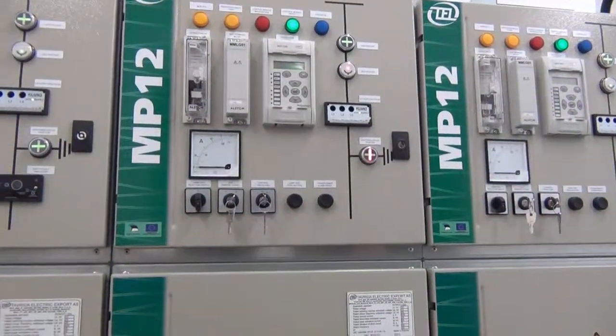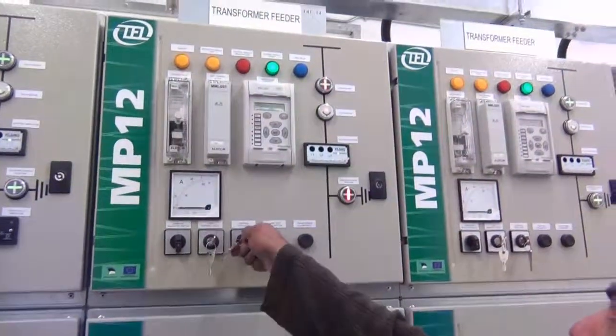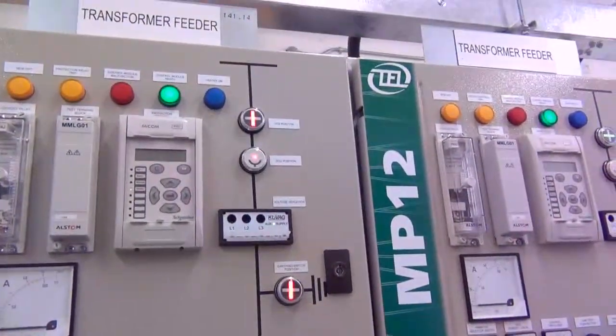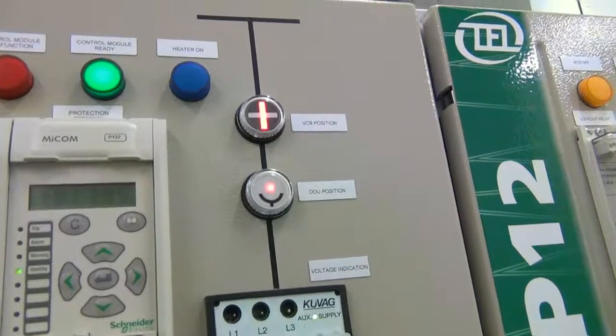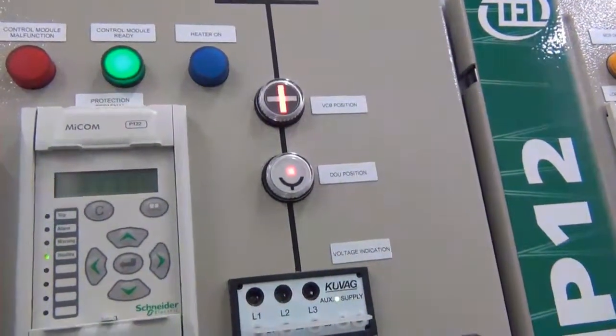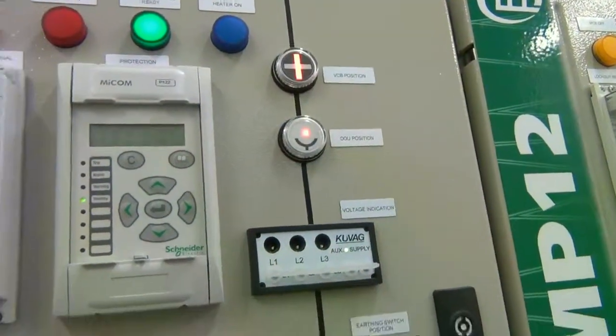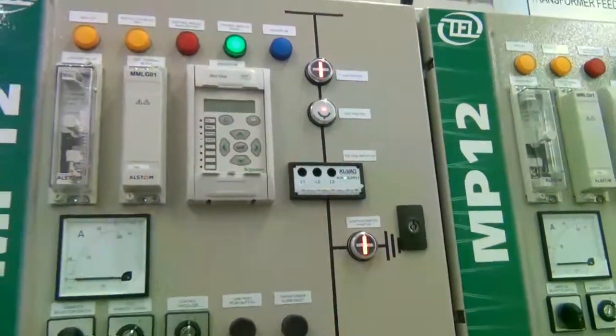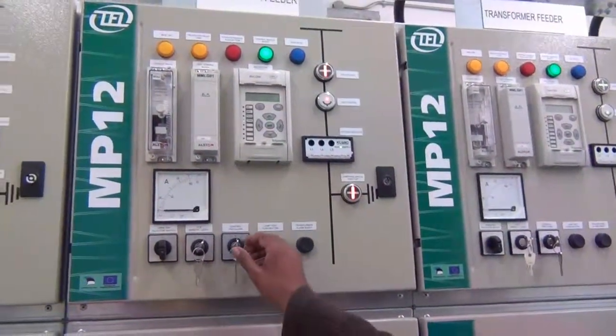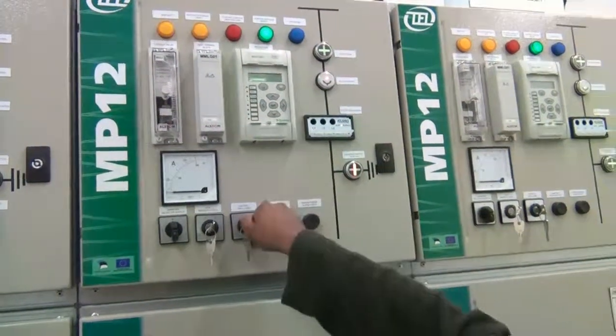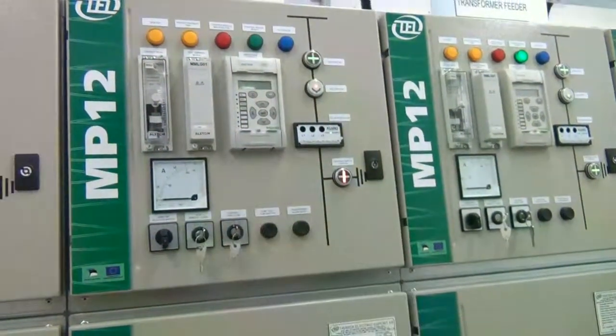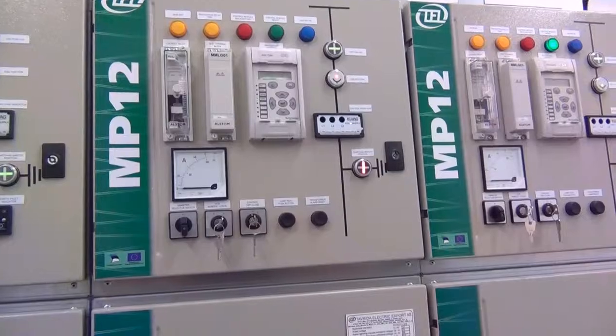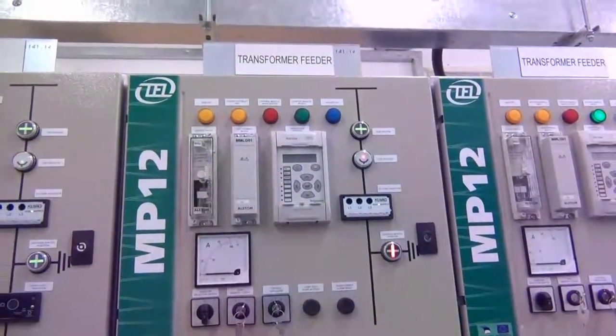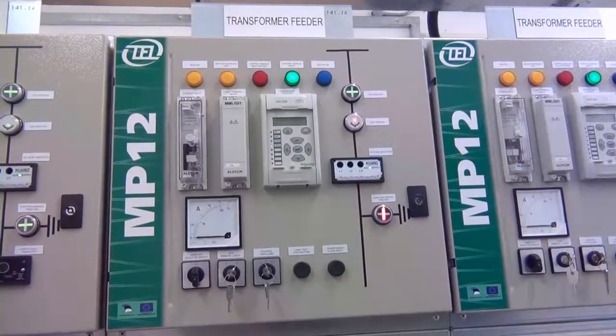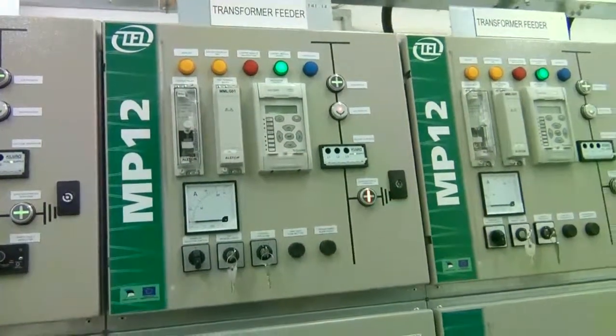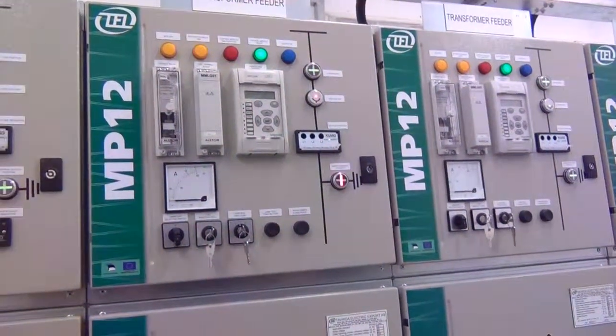We'll first close the breaker. Just give a close command and you see the VCB position is in closed condition. What we would also like to see is whether OCO operation can be carried out immediately. So we'll try and see the OCO operation. Open, close, open. The same can be seen. The control module takes around 5 to 7 seconds. It's again turned green, ready for the next open, close, open operations.